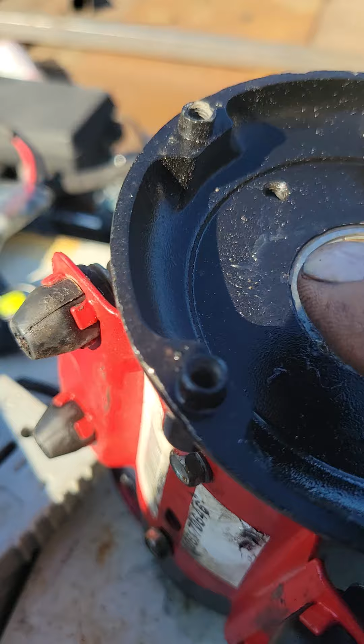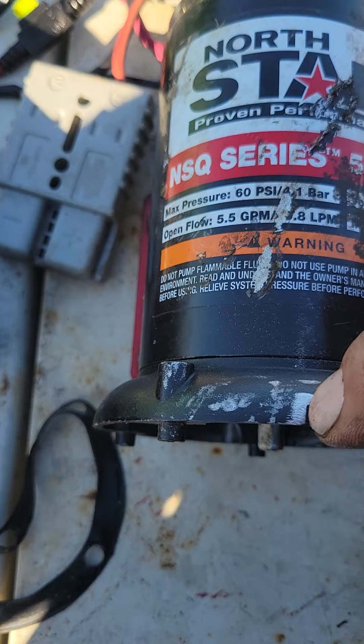But you want to create a relief in this housing, so when this pump starts to leak and fills this up, it's got some place to go other than your motor. So what I did was I took this cutoff wheel, see it's very thin, and I cut a relief in that housing. It doesn't have to be much, but you want it kind of small, and I put it on the top for a reason. So then when this builds up pressure, it's going to squirt the liquid through this little slot and hopefully squirt it up about 6 inches to where I see it.